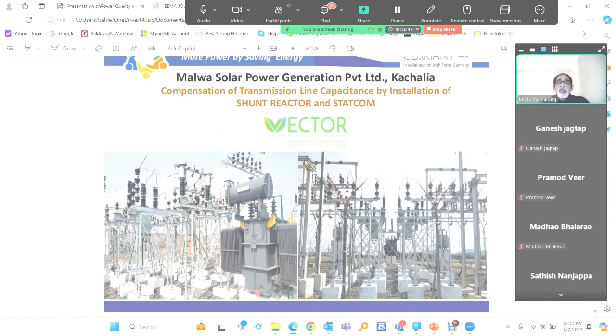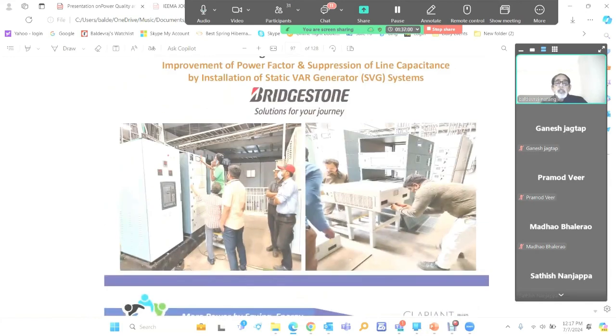Their demand was about 10 times what they were having internally, and power factor was 0.2 leading. So they were paying 60-70 lakhs per month in penalty. There we supplied one shunt reactor and one STATCOM at low voltage, and all the penalties were removed. Then Bridgestone, we supplied STATCOM at low voltage to get unity power factor.